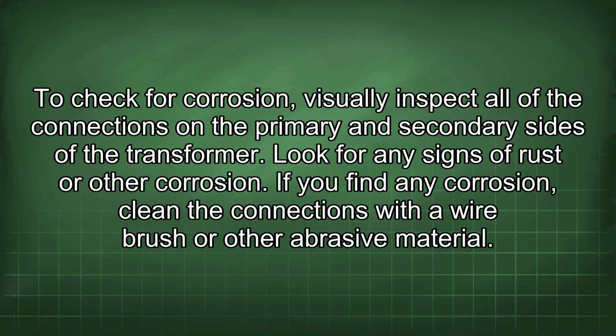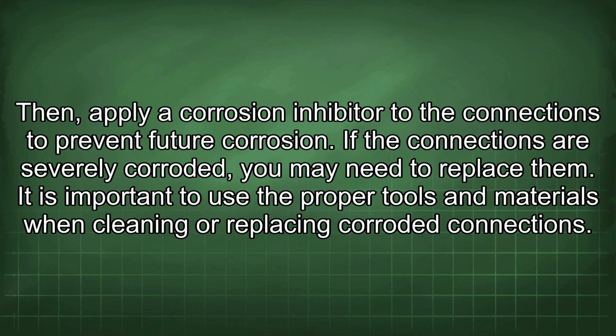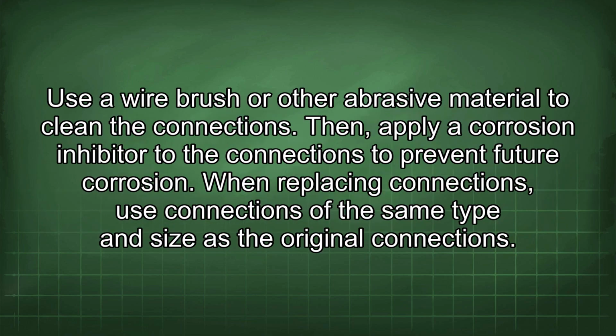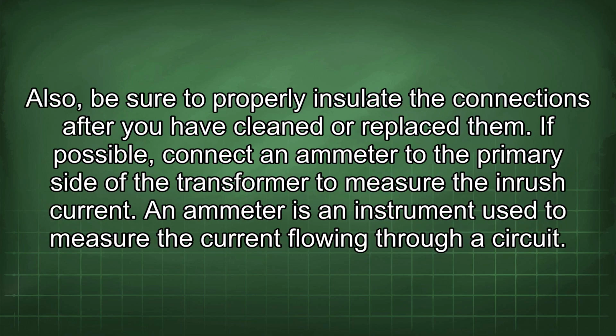If you find any corrosion, clean the connections with a wire brush or other abrasive material. Then, apply a corrosion inhibitor to the connections to prevent future corrosion. If the connections are severely corroded, you may need to replace them. It is important to use the proper tools and materials when cleaning or replacing corroded connections. Use a wire brush or other abrasive material to clean the connections. Then apply a corrosion inhibitor to the connections to prevent future corrosion. When replacing connections, use connections of the same type and size as the original connections. Also, be sure to properly insulate the connections after you have cleaned or replaced them.